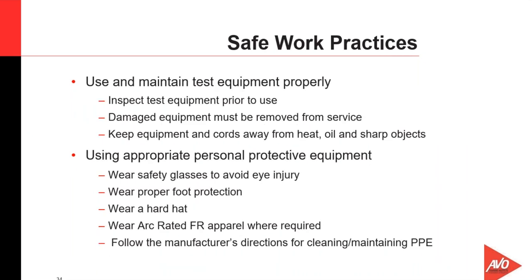One of the things to be said here is to make sure we understand the equipment that we're using. High voltage test equipment and high current test equipment may be fairly complex, so test technicians should be trained in the proper use of it, and also to be able to inspect and determine if it's actually functioning properly. If the equipment is determined to be damaged in any way, or the control circuits or anything are not functioning properly, then the equipment should be taken out of service and not used for the test.